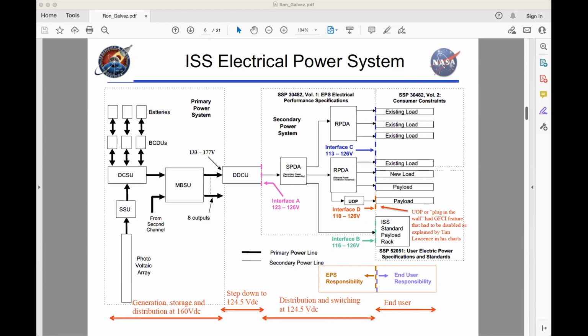So you couldn't command it, couldn't open or close the switches, couldn't do anything with it. At some point, 2 of those boxes, out of 4 total affecting 4 power channels, had this issue where we could not communicate with the box, all because of the EEPROM issues.